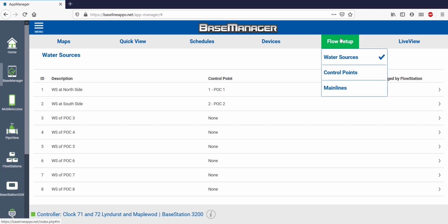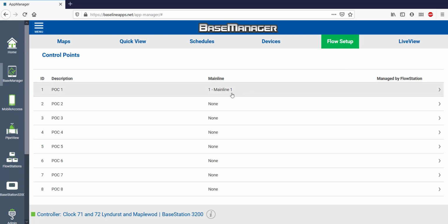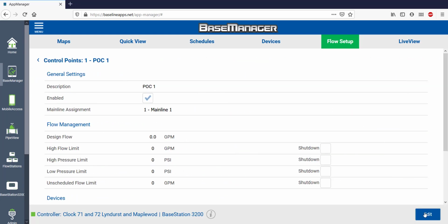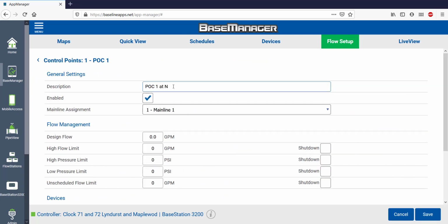The next item to set up within Flow are control points. I'll be working on control point 1, so open it and then select Edit. I'm going to name control point 1 and reflect its location. This control point is already associated with mainline 1, although I could associate it with different mainlines on more complex systems. Now to my flow limits.